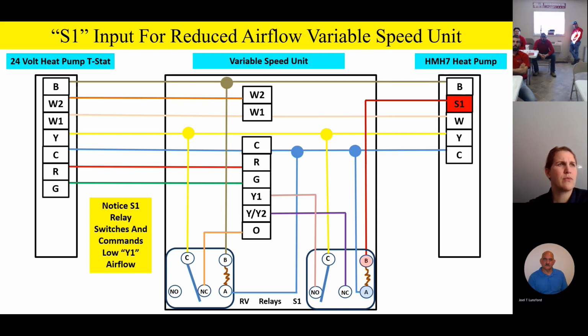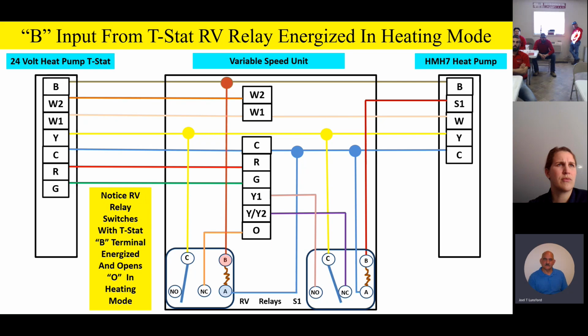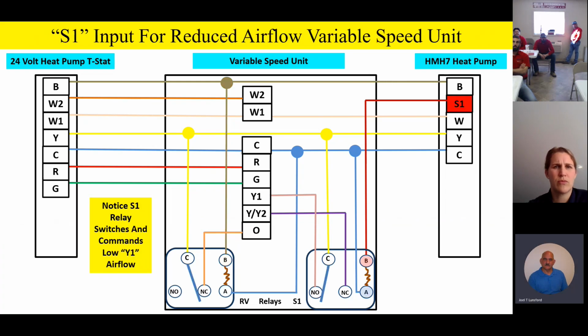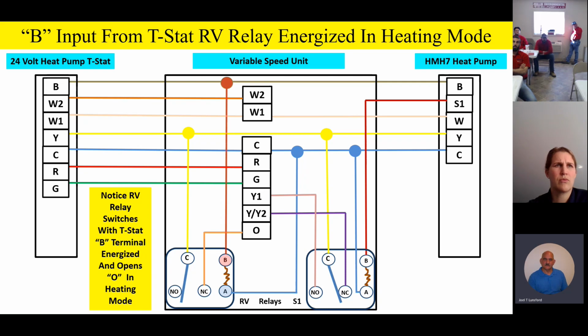Everybody's happy. Now let's say, for instance, the thermostat goes into the heating mode of operation. What it's going to do is energize the B terminal. It'll then switch the RV relay, and it'll break that 24 volts to the O terminal inside. Because remember, the only thing that RV relay is doing on the left-hand side is, when we go to the heating mode, bang, we energize B, you switch that relay, and you kill that O signal inside, because now the indoor unit recognizes the system is in the heating mode because it doesn't see the O signal. So the O signal has two functions on the indoor unit.